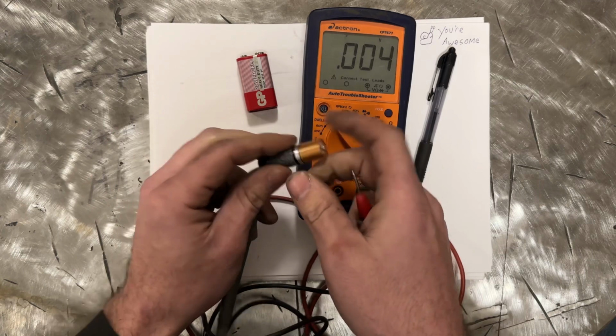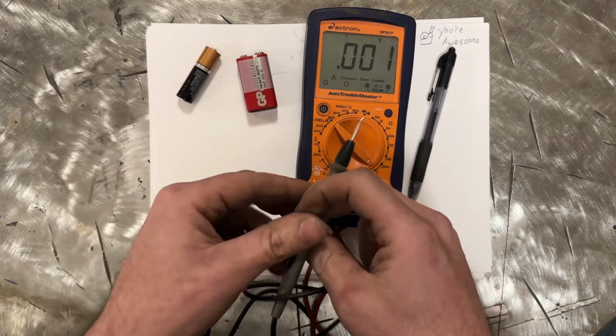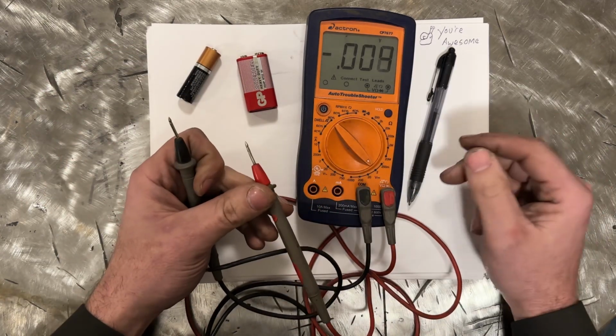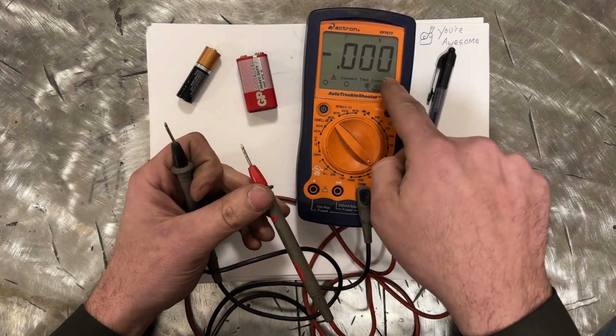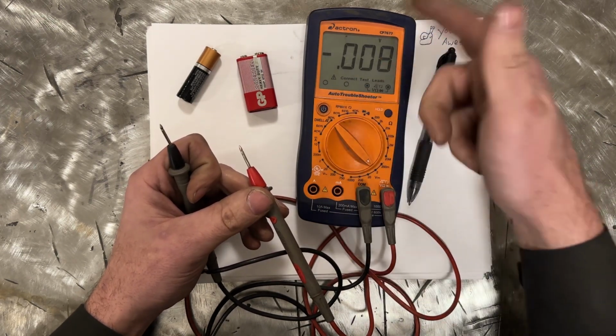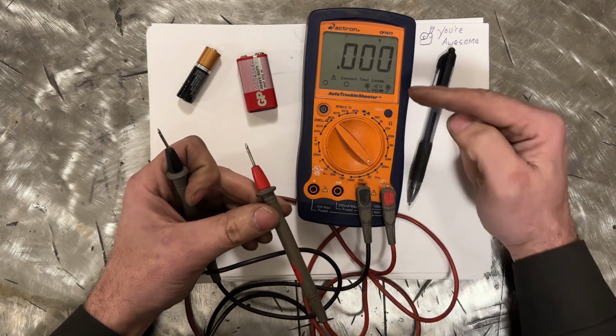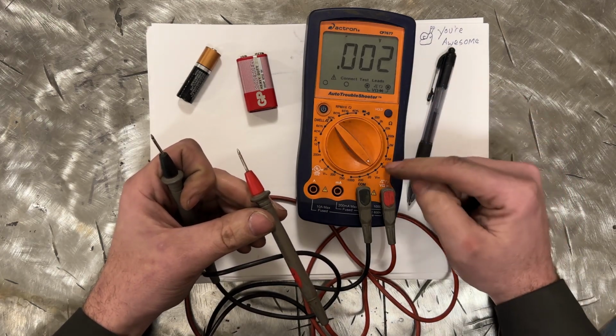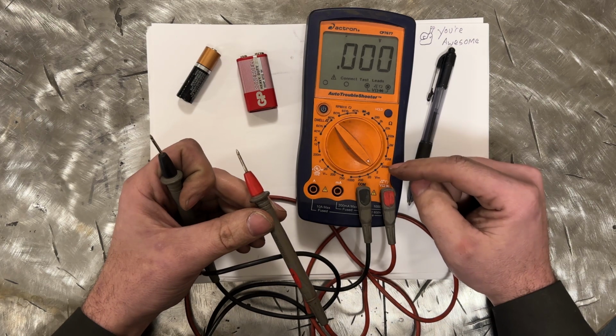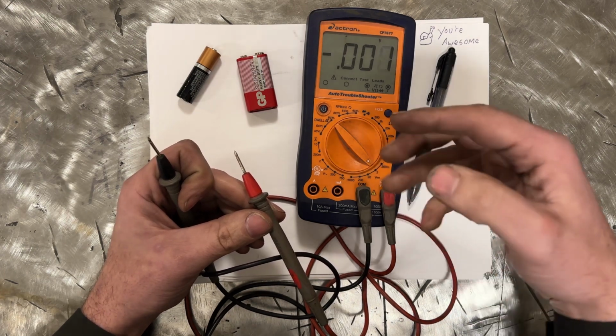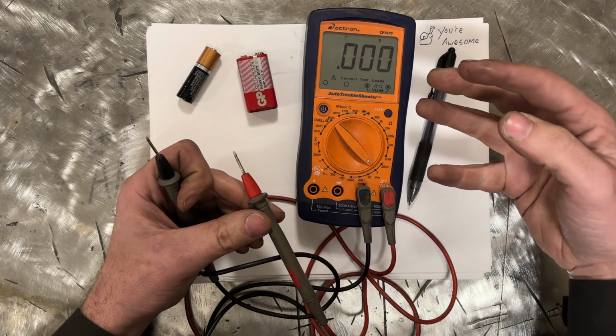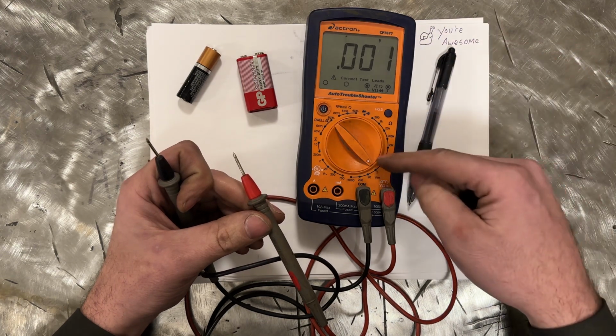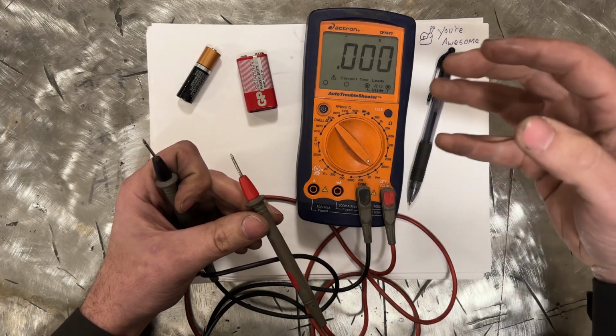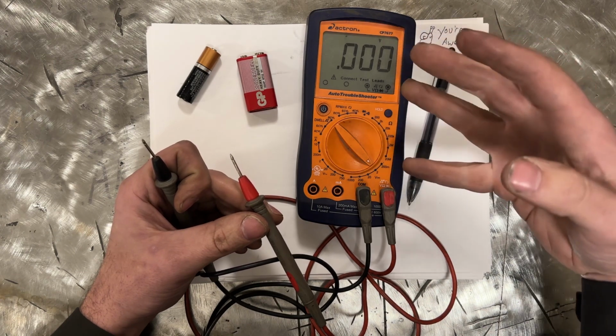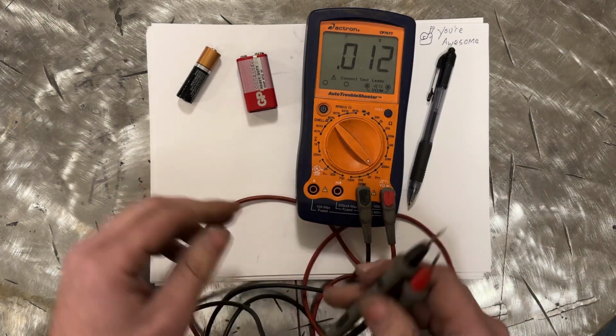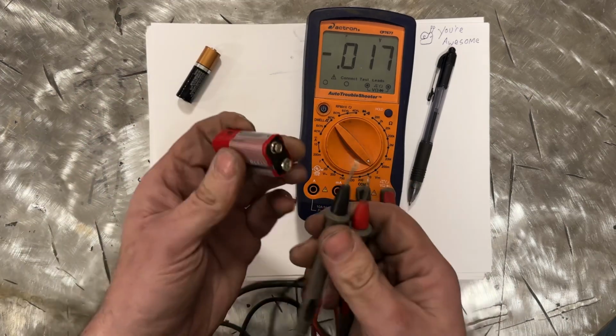That's extremely important if you're testing sensitive electronics that operate in a very narrow window. And yeah, you can see it's going to self-clear itself. Yeah, see, it's going to zero itself out. If you're testing sensitive electronics, you want to be in a scale that it works. Like on the 200 millivolt, if your electronic that you're testing is 100 millivolts, well, if you read it on too high of a scale, you might think it's okay, and it might not be. So be aware of scales.